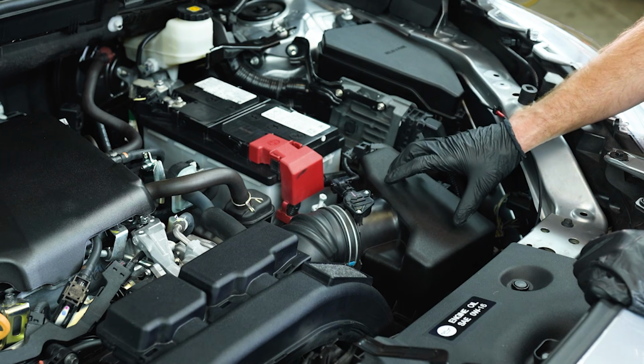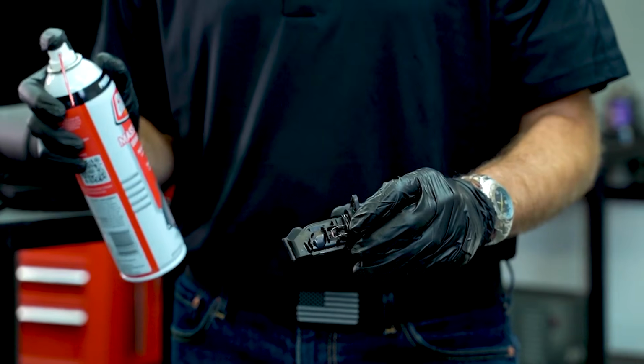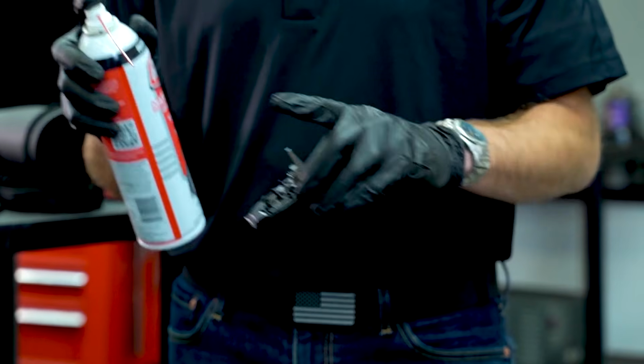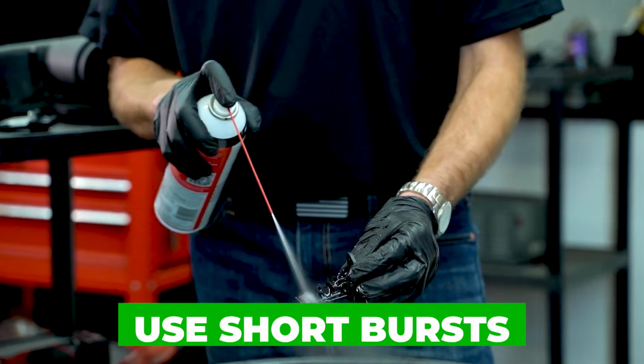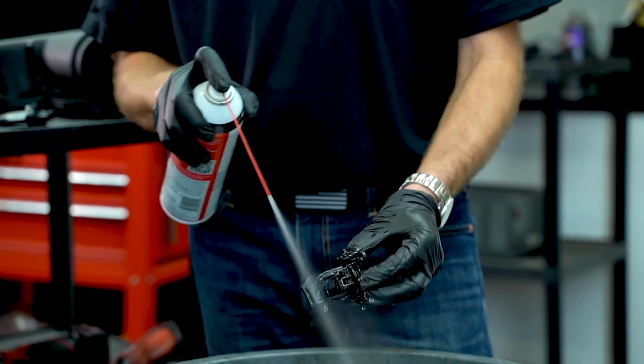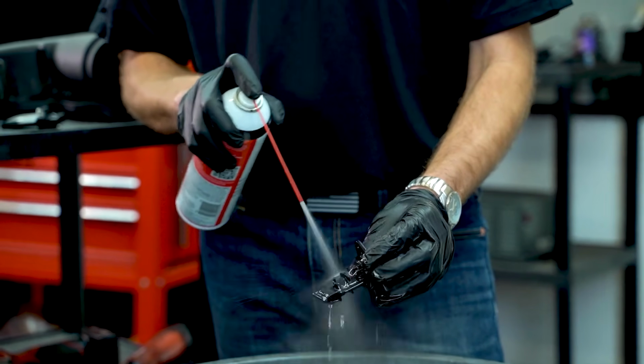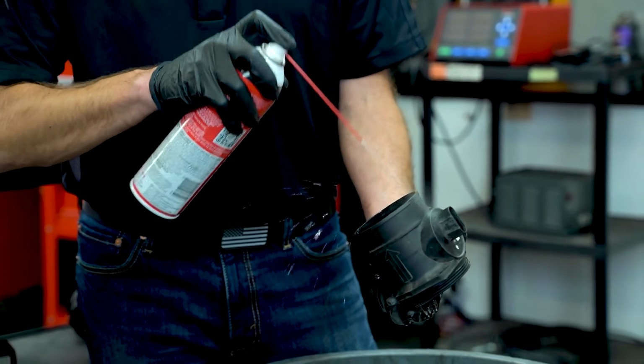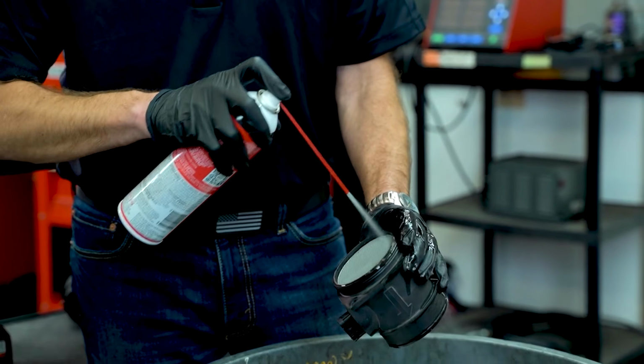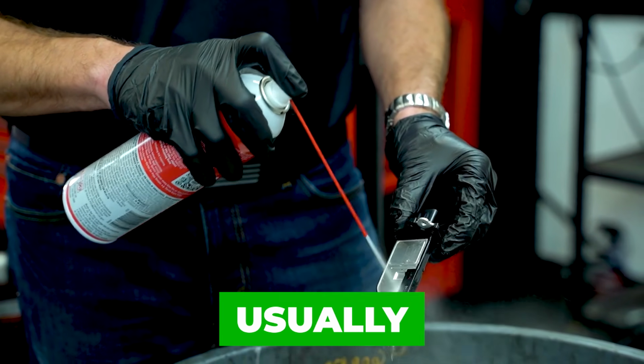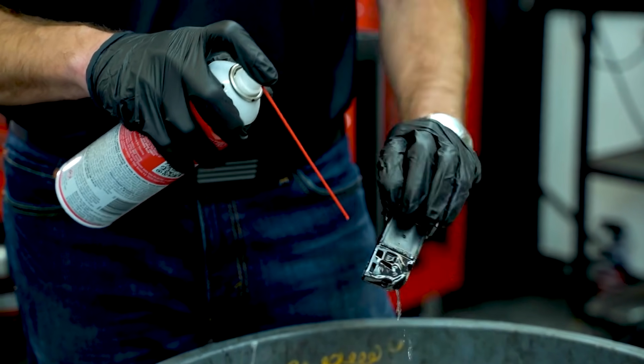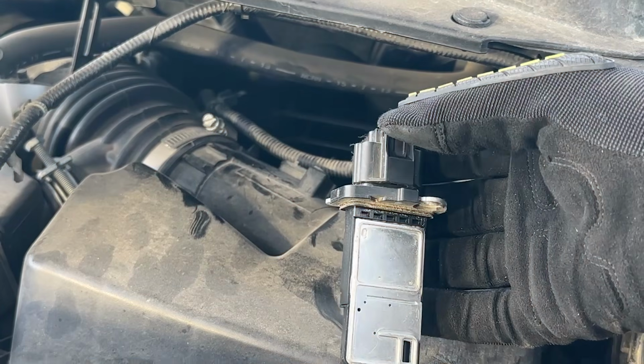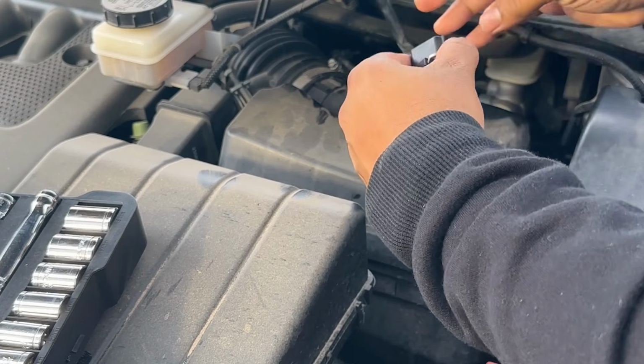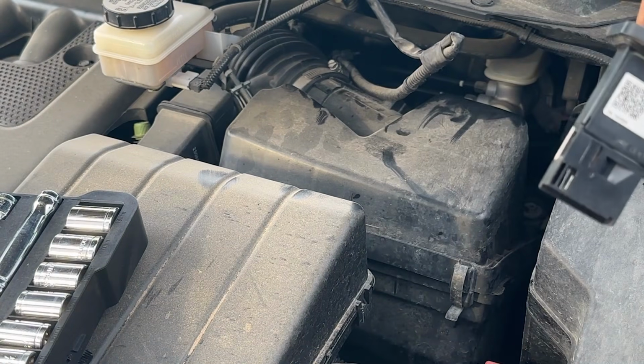Hold the sensor by the housing only. Spray the cleaner from 4 to 6 inches away. Aim directly at the sensing element. Use short bursts, not a continuous blast. Rotate the sensor to let gravity carry contaminants away. No shaking, no wiping, no extra passes just in case. Usually 6 to 10 sprays total, less than 20 seconds. More spraying does not mean more cleaning. It means more risk. This is where most DIY jobs fail.